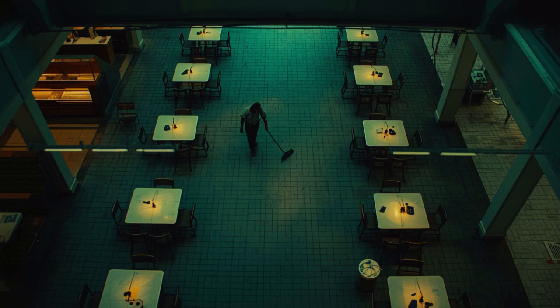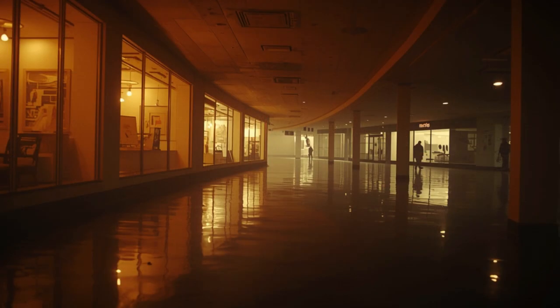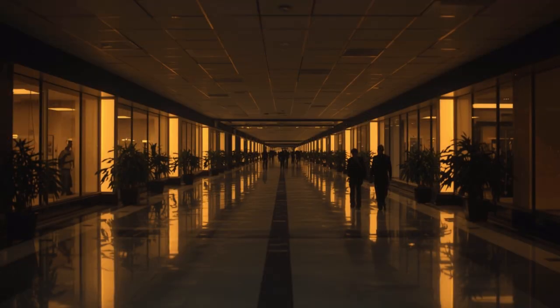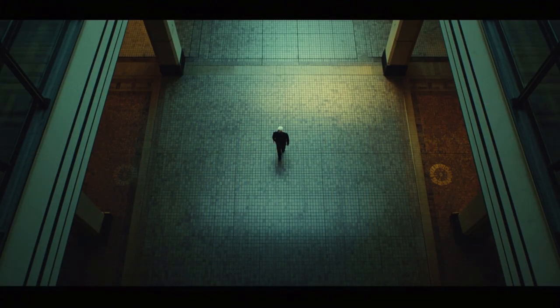The atrium smoke control system typically consisted of a combination of large exhaust fans mounted at the top of the atrium space, capable of withdrawing smoke from the upper reservoir at a controlled rate, and make-up air inlets at lower levels, admitting fresh air to replace the exhausted smoke and maintain the clear layer near the floor where occupants were moving toward exits.